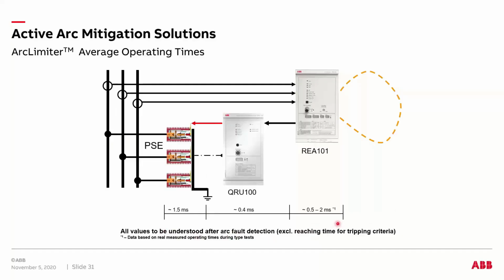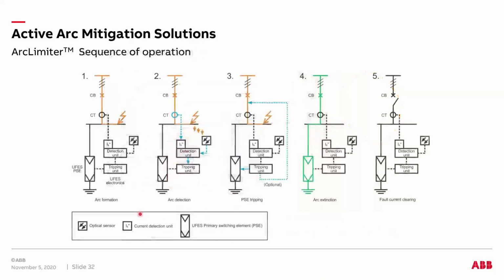So in total, about 4.5 milliseconds, you are converting this arc flash incident into a bolted fault by creating a low impedance path, so that your upstream fuse or a breaker can operate and isolate this bolted fault within your system.